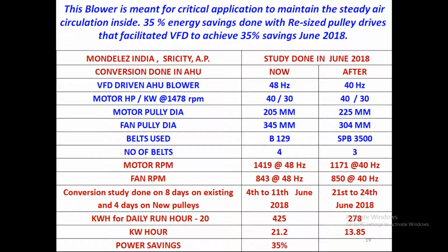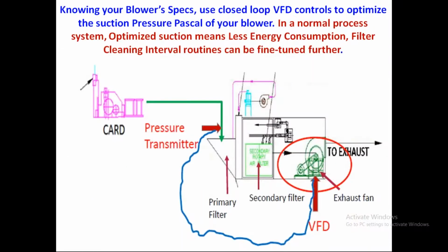It is not only for the comfort zone I am talking about, it is for critical applications like a blower, an ID fan impeller, an ID fan blower for a boiler, or a critical application like an air washer, or a blower in this type of food processing industry, where the air input and output and the air changes within the premises are more important to maintain hygiene for food processing.